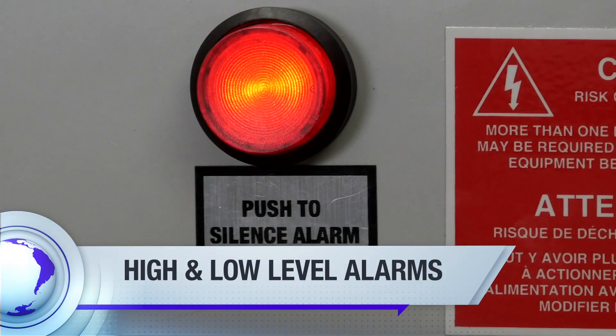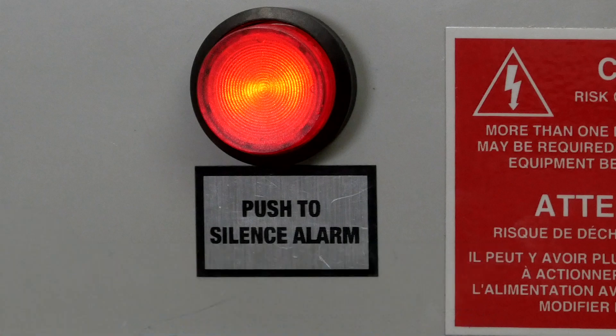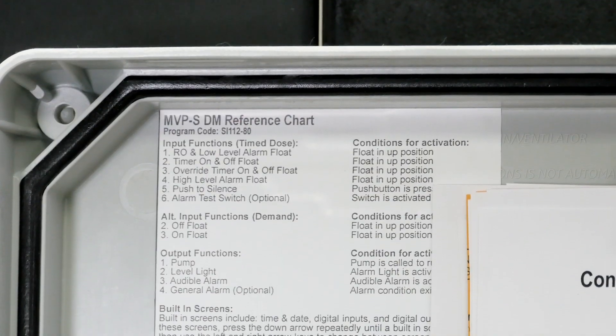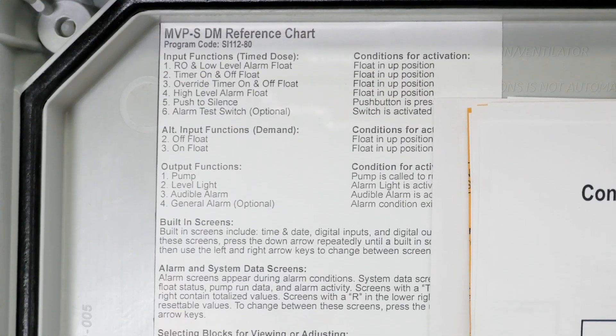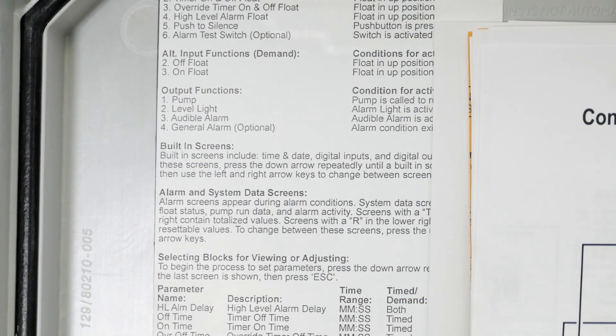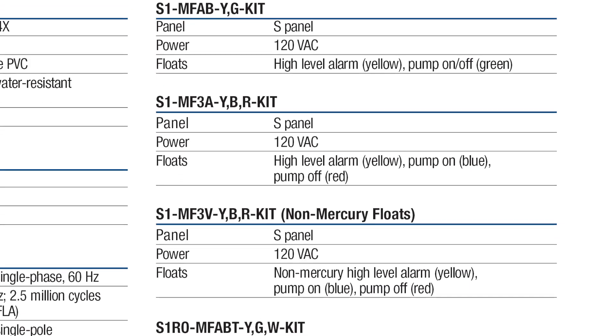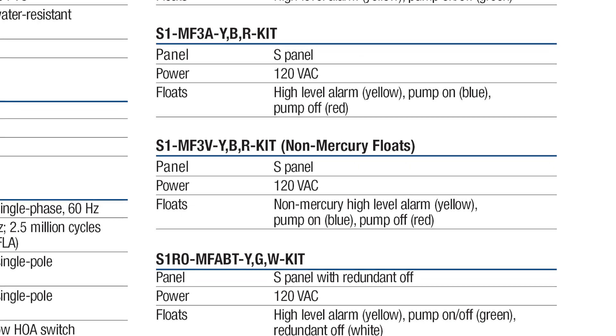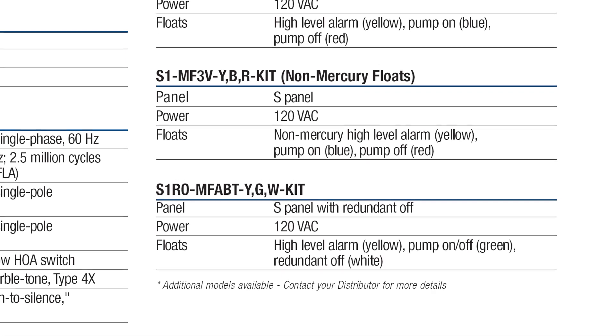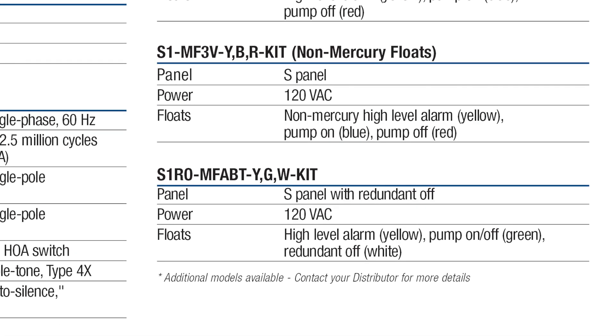High and low level alarms serve as a warning and are an integral part of the Orenco control panels. While every MVP and VCOM panel has a high level alarm, not every electromechanical panel has a low level alarm. Please check to see whether your panel has a low level alarm. If the panel model number contains the letters RO, your panel includes a low level alarm. If it does not, then all alarms will be high level alarms.